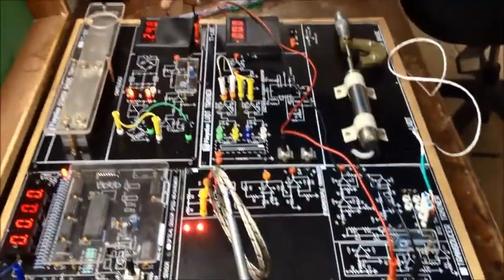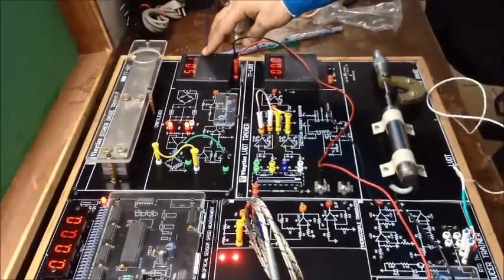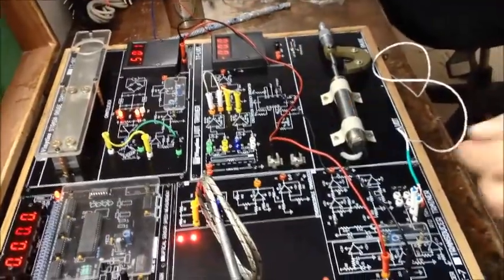As you can see it is around 250 grams or 248. Now we will load the complete set and the total physical weight is around 500 grams — you can see the result is around 501, that is almost approximately 500 grams. This one gram error can be adjusted through this port.